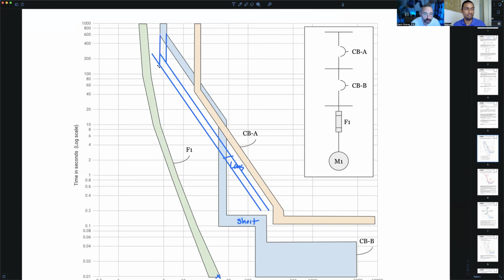So now our redrawn curve would look like this with a decrease in time delay for the long time trip. Looks good, that would also be a correct answer choice if presented to us. And look, all of this blue area we've shifted down by decreasing the time delay. In the new shape, we no longer have miscoordination. So this would be the area of our new long time trip region for circuit breaker B in blue, which would also be perfect.